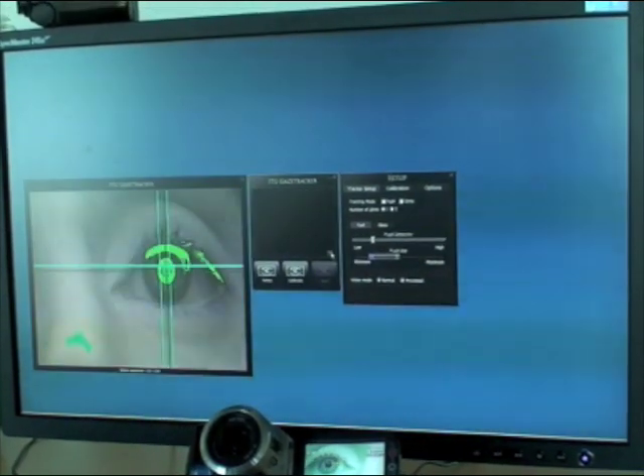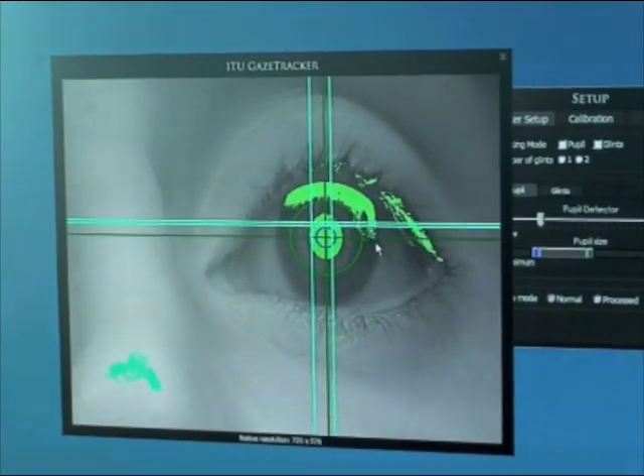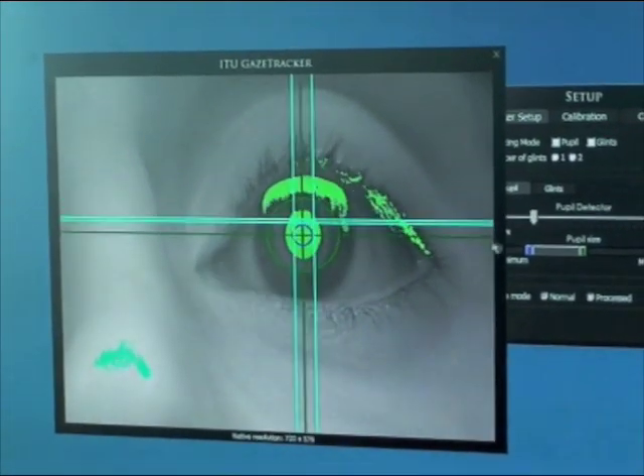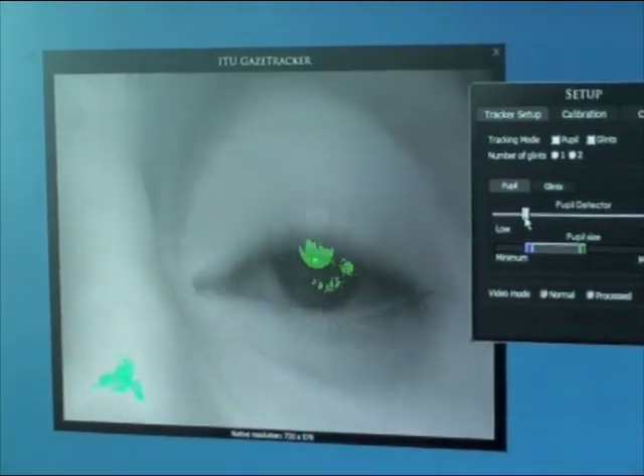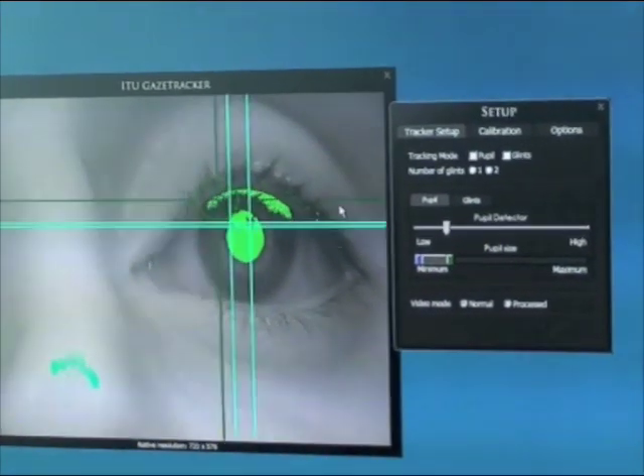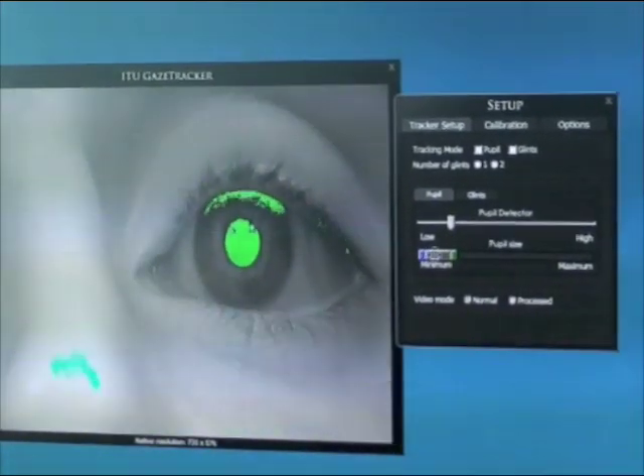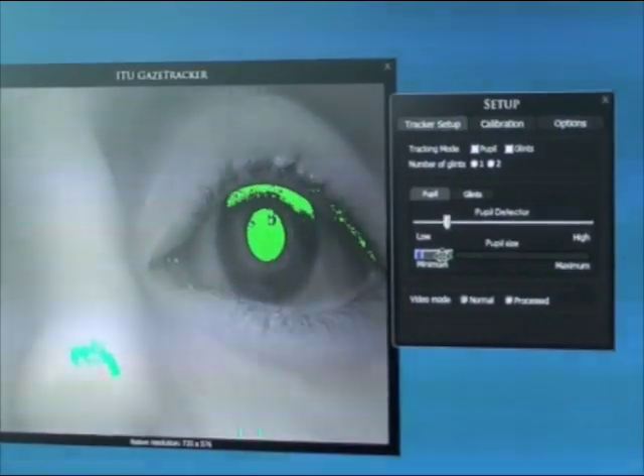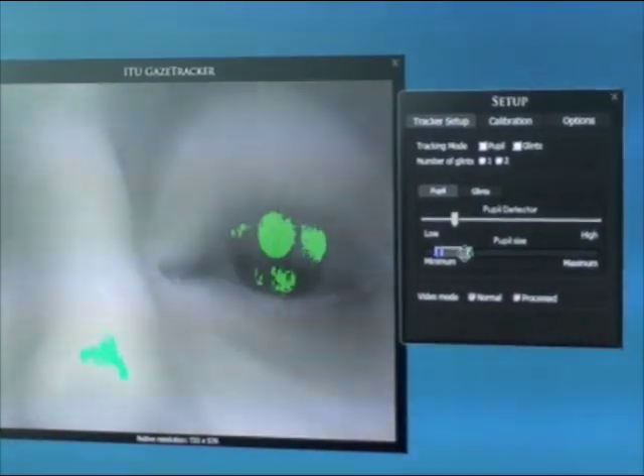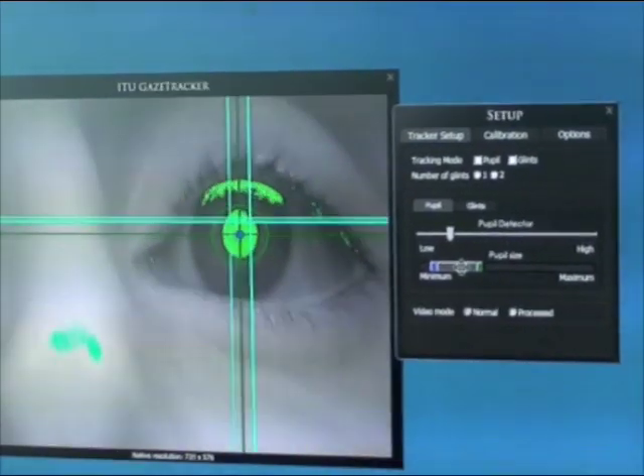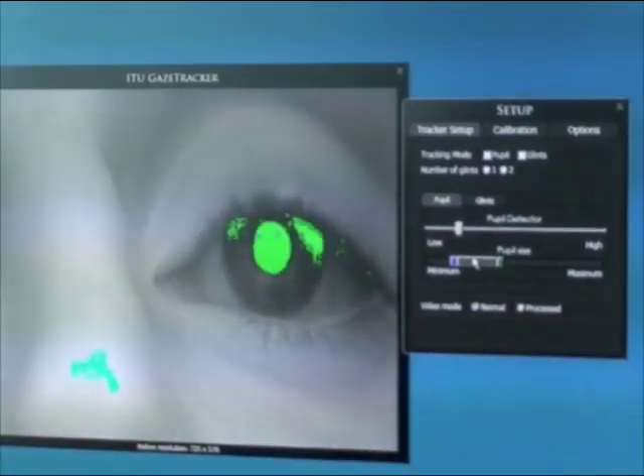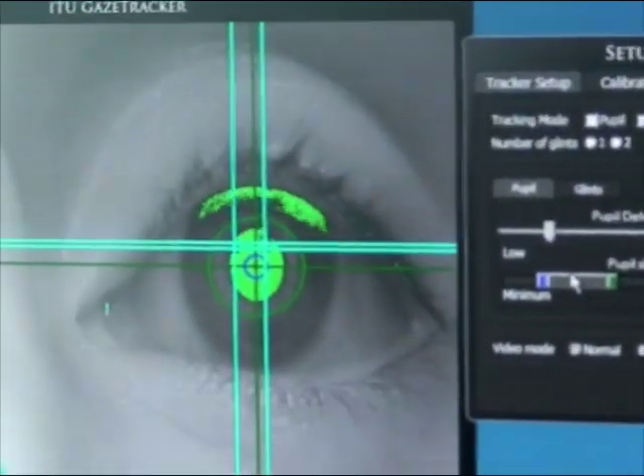We can launch a bigger window of the eye by pressing the resize button. This will make it easier to tweak the parameters of the eye tracker. If the pupil is not properly detected we can see blinking crosses as an indication. We can tweak the pupil size parameters using the slide bar — the minimum and maximum pupil size are represented by two circles: minimum by a blue circle and maximum by a green circle.